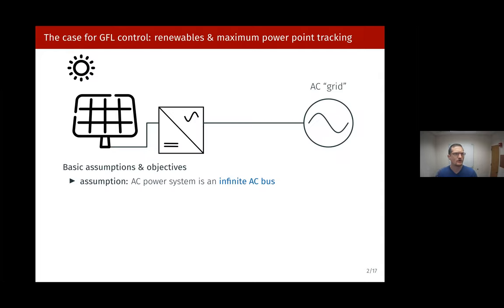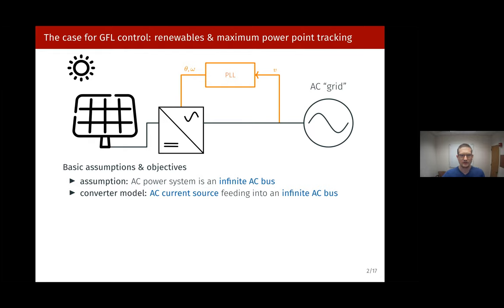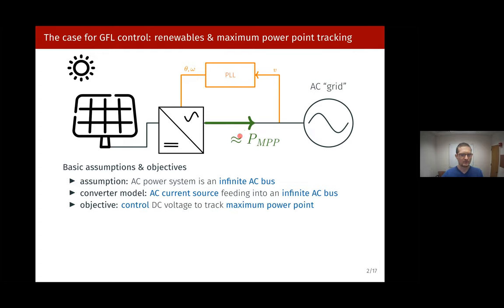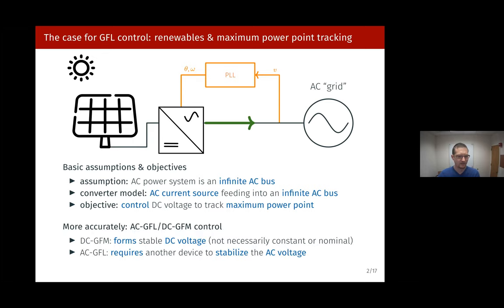Why do we even need grid following control in the first place? The one use case where you genuinely need the standard grid following architecture with a PLL — assuming the AC grid is an infinite bus creating a perfect sine wave, locking on with a PLL, and controlling the converter as a current source — is maximum power point tracking for renewables. Using PV as an example, you control the power injection into the AC grid to stabilize the DC voltage seen by your PV panel so it generates maximum power.